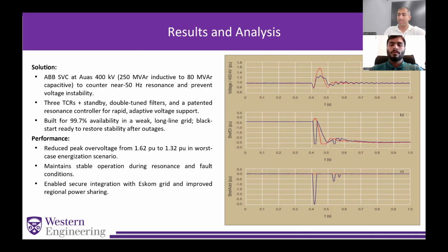So, an ABB SVC rated to 250 MVAr inductive to 80 MVAr capacitive uses three TCRs plus standby double-tuned filters and a resonance controller to target near 50 hertz dynamics, built for 99.7% availability, which is a very good number. It tames overvoltages during energization and faults, cutting worst-case peaks from the previous 1.62 per unit to 1.32 per unit. That stability enabled secure interconnection with Eskom and safer regional power sharing across very long lines, as I mentioned, 890 kilometers.